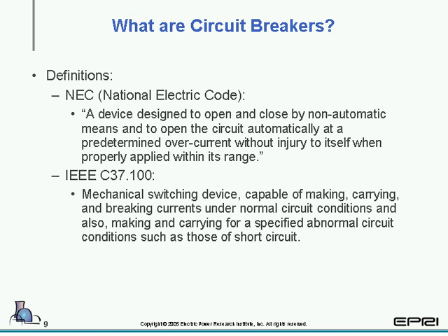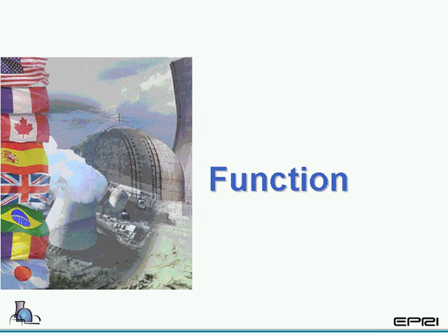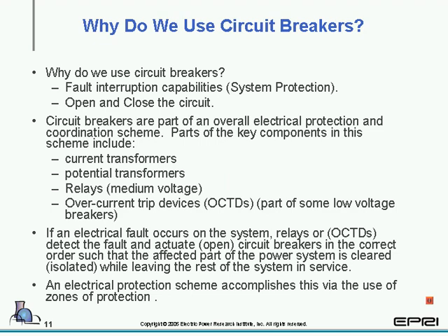The NEC defines a breaker as a device designed to open and close by non-automatic means and to open the circuit automatically at a predetermined overcurrent without injury to itself when properly applied within its range. And the IEEE C37.100 defines a breaker as a mechanical switching device capable of making, carrying, and breaking current under normal current conditions, and also making and carrying for a specified abnormal circuit condition such as those of short circuit. That's the definition. We'll take a look at the function.